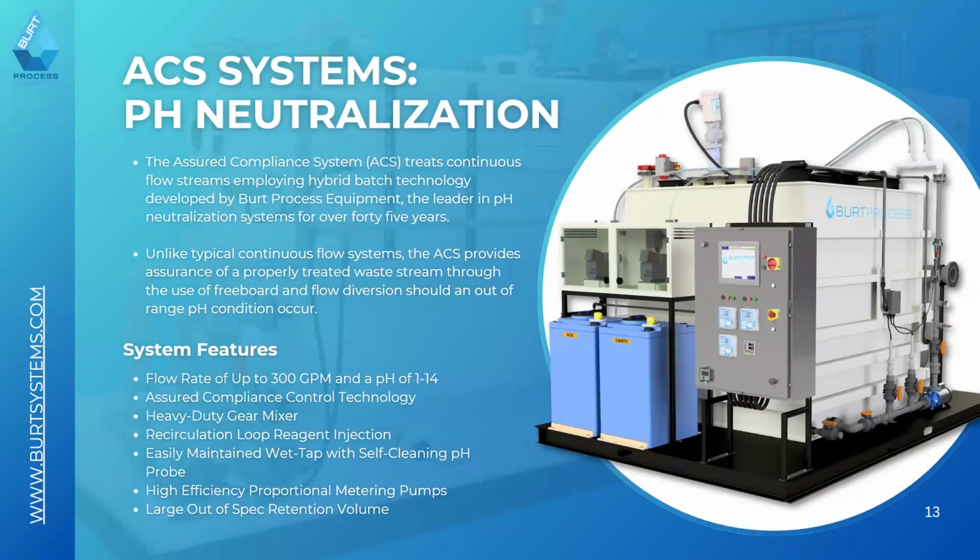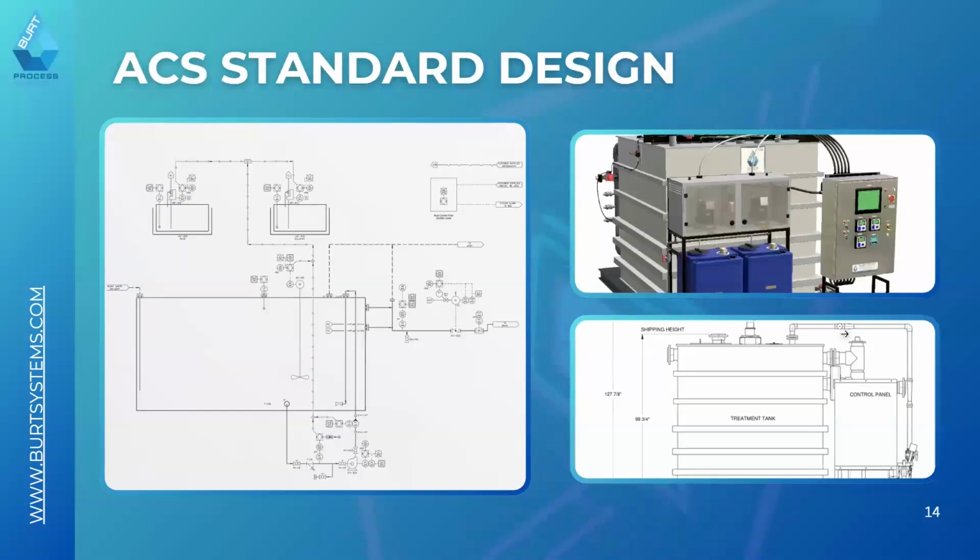It's using the waste as a carrier medium, so that rather than having a basic drip injection into your pH system, you're doing a recirculation with the waste, pressurizing it and ducting it into the mixer backwash, which really rapidly speeds up your injection, and speeds up your pH treatment process.